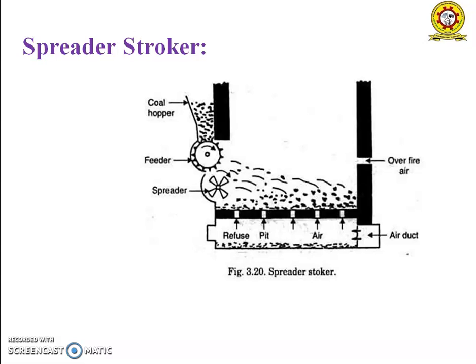The air is admitted from the underside of the grate, which is divided into several compartments each connected to an air duct. The grate must be saved from being overheated. For this, coal should have sufficient ash content which will form a layer on the grate. Non-caking coals are best suitable for the grate. The rate of burning with the stoker is 200 to 300 kg per meter square hour when forced draft is used.